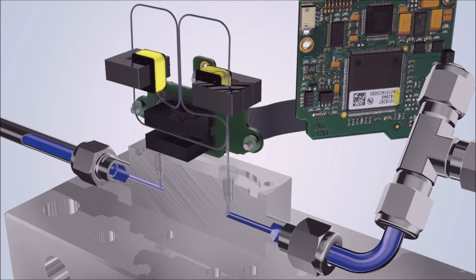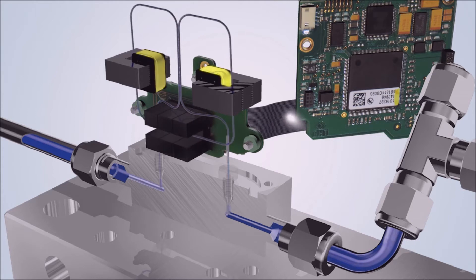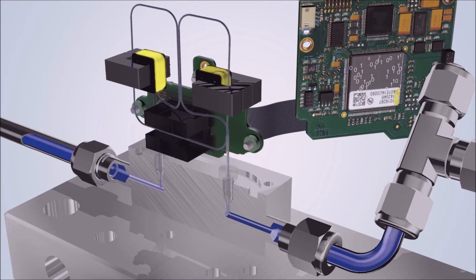A signal is then transmitted to the digital electronics, which translate the measured vibrational value into a mass flow value, and compares this to the set point from a PC, PLC or analog port.